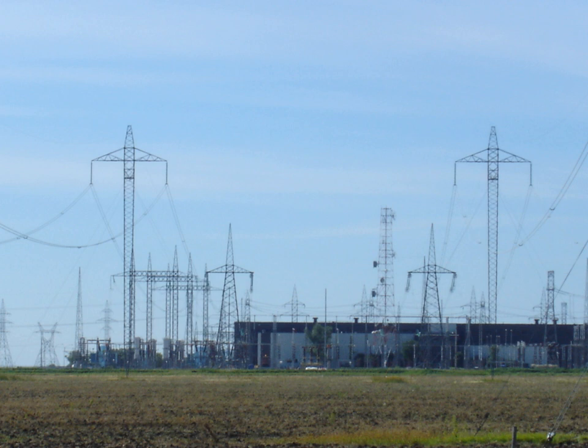Depending upon the environmental conditions and the performance of overhead line insulation, it may be possible for a given transmission line to operate with a constant HVDC voltage approximately the same as the peak AC voltage for which it is designed and insulated. The power delivered in an AC system is defined by the root mean square (RMS) of an AC voltage, but RMS is only about 71% of the peak voltage. Therefore, if the HVDC line can operate continuously at the peak voltage of the AC equivalent line, then for a given current, the power transmission capability when operating with HVDC is approximately 40% higher than when operating with AC.